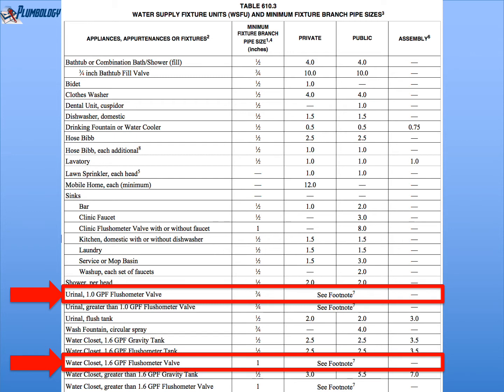We see urinal, one gallon per flush, flushometer valve. Comparing those two to the others — like water closets, gravity tank — notice that gravity tank water closets are given a set fixture unit value. The table says all gravity tank water closets are 2.5 fixture units. The flushometer tank, or pressure-assisted tanks, are 2.5 for public and private use, 3.5 for assembly use. But for the two highlighted entries — the urinal and water closet flushometer valves — they don't give a value. They say see footnote number 7. So on the next slide we'll look at footnote number 7.